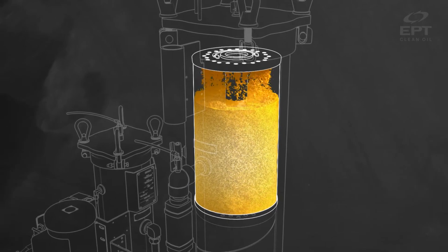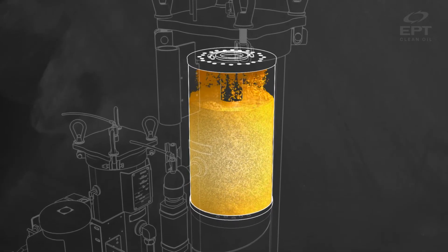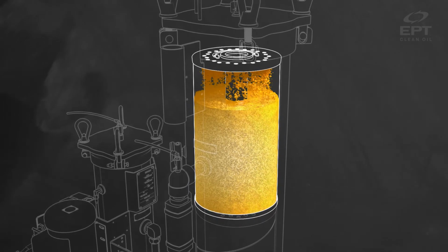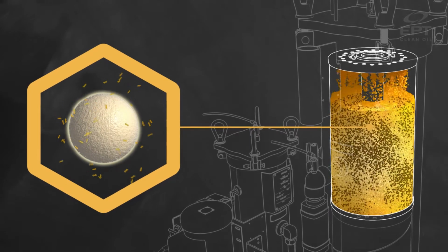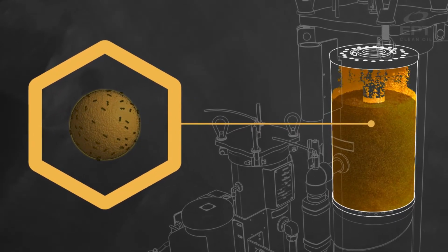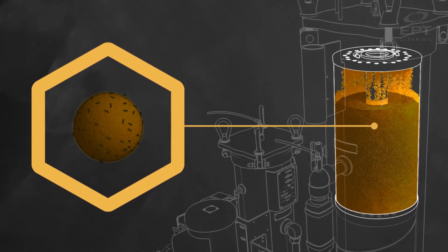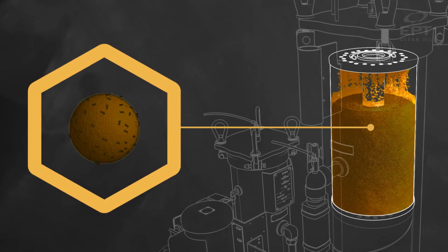Addressing the chemistry in your fluid, the ICB filters remove dissolved breakdown molecules that have formed as part of normal fluid breakdown. By cleaning the oil, ICB filters also restore lubricant solvency. This reverses the varnish formation cycle, removing pre-existing varnish deposits via chemical equilibrium.